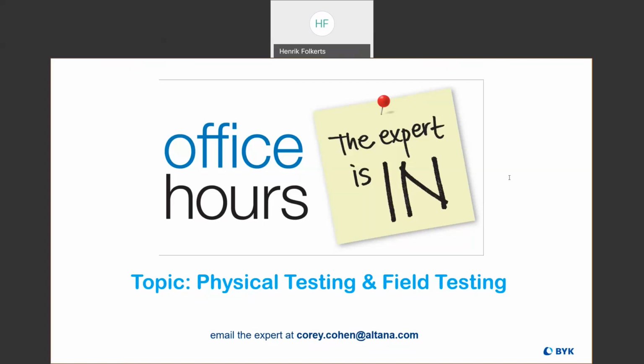I'd have to check exactly what it is, but those oils can be used to test the accuracy of your viscosity measuring tools. So you can take a measurement of the viscosity of the standard oil, using your flow cup, say, and make sure that the reading you get matches what's printed on the certificate to within a certain tolerance. Yes, both calibrations and calibration checks are important to do regularly to make sure that your tools are measuring accurately. Great. Thank you, Corey.